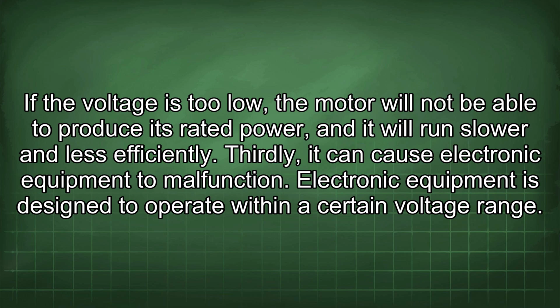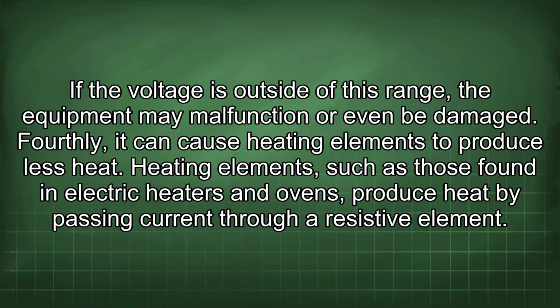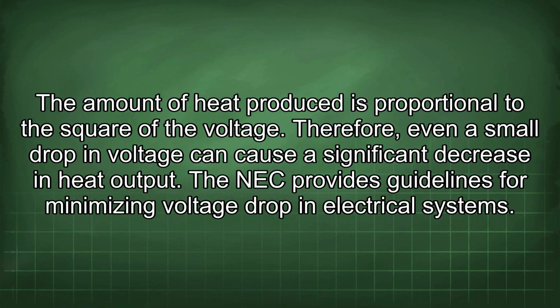Thirdly, it can cause electronic equipment to malfunction. Electronic equipment is designed to operate within a certain voltage range. If the voltage is outside of this range, the equipment may malfunction or even be damaged. Fourthly, it can cause heating elements to produce less heat. Heating elements, such as those found in electric heaters and ovens, produce heat by passing current through a resistive element. The amount of heat produced is proportional to the square of the voltage. Therefore, even a small drop in voltage can cause a significant decrease in heat output.